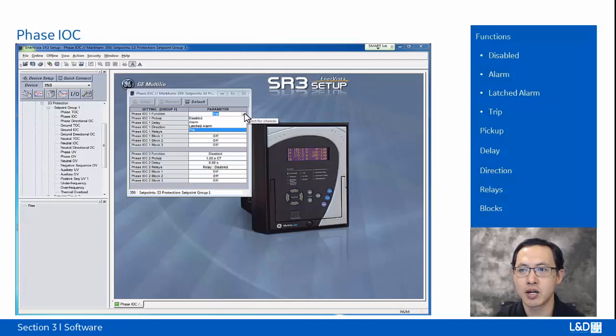If the function is set to Alarm, it means this feature is operational. And when the alarm happens, this function will operate the selected auxiliary relays, and the LED on the front panel will flash on alarm. And the alarm condition will self-reset when the operating condition is cleared. If the function is set to Latched Alarm, the whole operation is similar to alarm, except that the condition will stay on even when the operating condition is cleared. So the reset button is needed to clear the alarm condition.